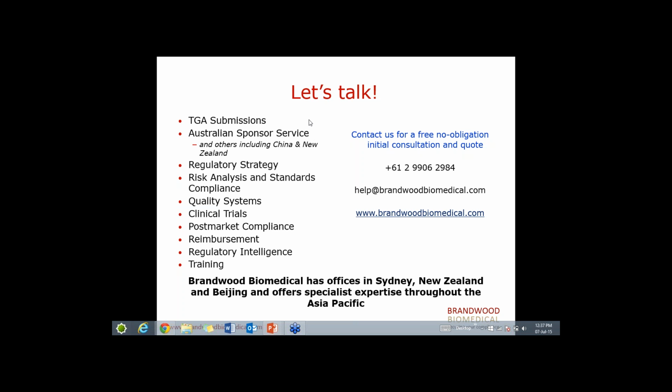Okay, so you would have heard an announcement earlier. There were plans to merge the two regulatory entities together under the ANZTPA, which obviously has halted, and that's not progressing. The main difference is that New Zealand accepts certifications from FDA, so overseas certifications from FDA and obviously Europe and Australia. However, Australia does not accept US or FDA approval. Australia only accepts the European.